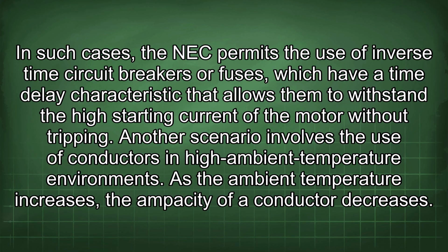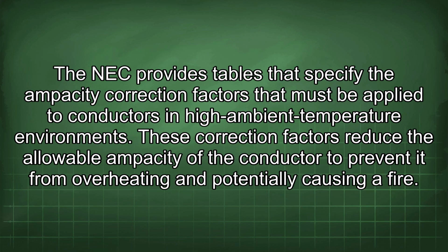Another scenario involves the use of conductors in high ambient temperature environments. As the ambient temperature increases, the ampacity of a conductor decreases. The NEC provides tables that specify the ampacity correction factors that must be applied to conductors in high ambient temperature environments.